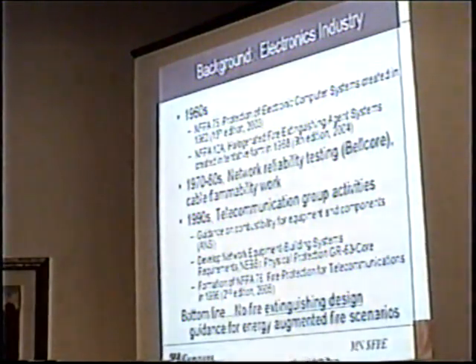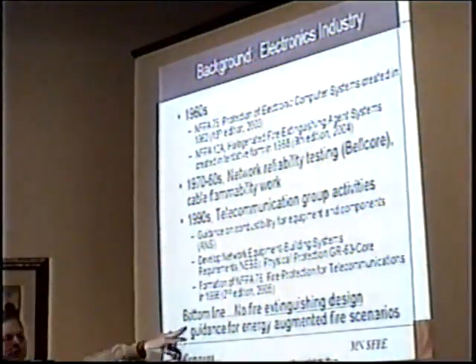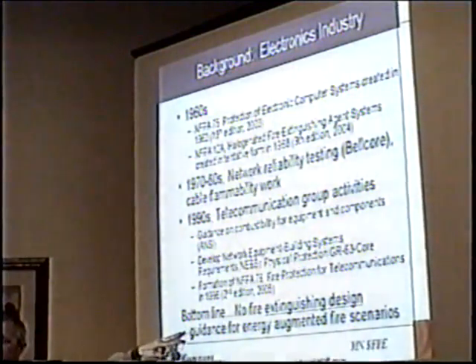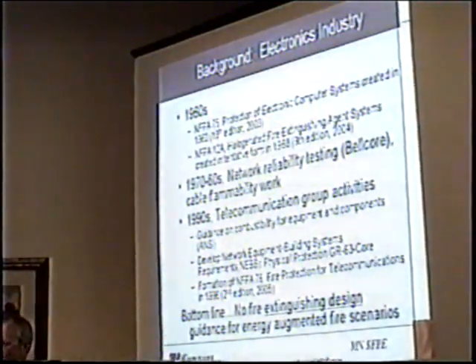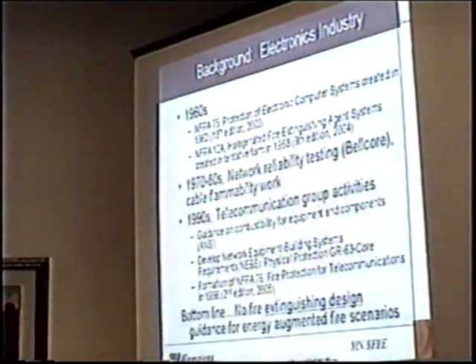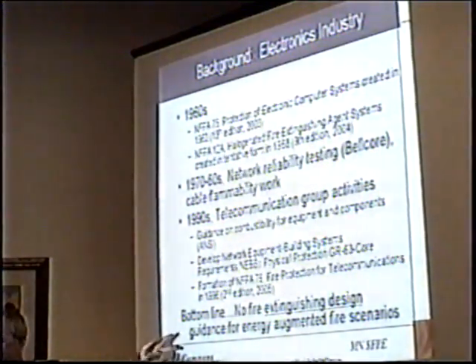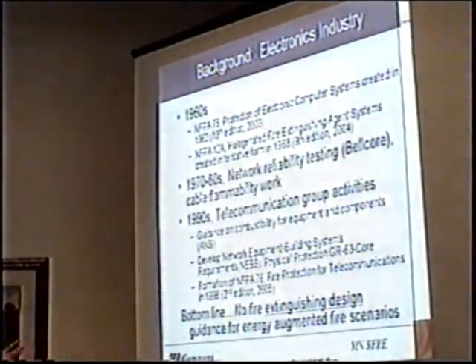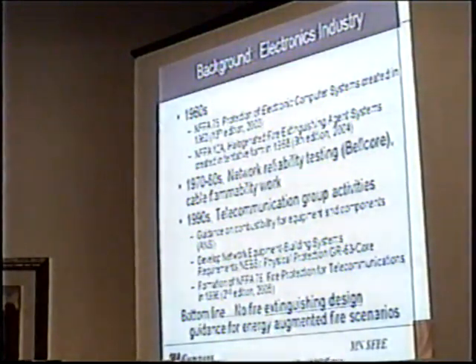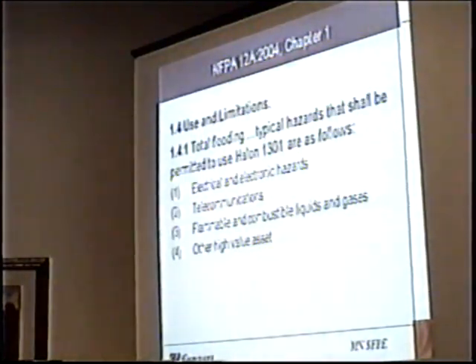The bottom line, there's no guidance on energy augmented fire scenarios and how to protect those. It's all passive protection. What do you do for suppression? We're using these gaseous agents, we're using sprinklers, we're using all kinds of things to protect them, but we really didn't have any guidance on it. We had no standards on this, through that whole point in time. Look at NFPA 12A, which I said was the 8th, 10th edition, whatever it is right now, 2004. This is what's in the standard right now.